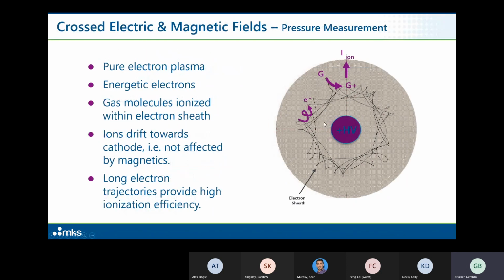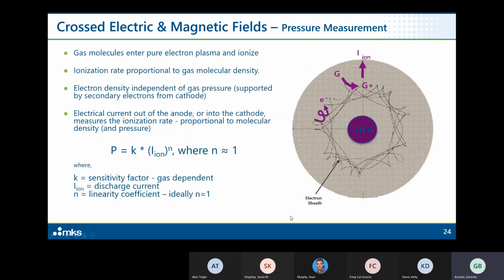So how does the gauge work? Well, we have our electron cloud, which is essentially an ionization region. If a gas molecule comes in and crosses that electron cloud, it gets ionized. And as soon as it gets ionized, the electric field pushes it to the wall, where it gets picked up as an ion current. So the ion current is the discharge current in the discharge, which, as we're going to see, is proportional to the gas pressure. Because we have such long electron trajectories in this device, we have very, very high sensitivities that allow us to measure pressures with cold cathode gauges down to 10⁻¹³ torr if you want. Of course, that's going to require much stronger magnetic fields that wouldn't be compatible with an analytical instrument, but it can be done. So anyway, this is kind of how it all boils down.